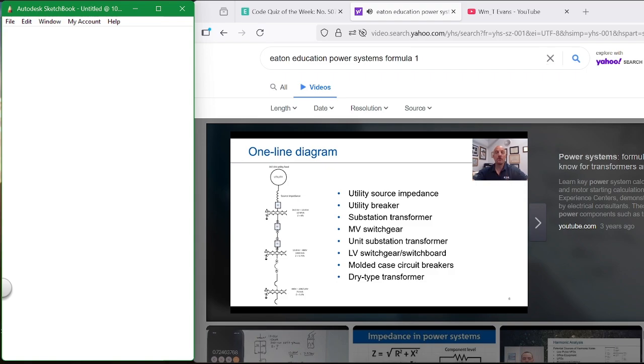So as a consultant, why do you need a one-line diagram like this one? Well, it's really important. If you're going to try to do calculations, you really need to have a good understanding of the actual numbers of values for the equipment. And there's two things associated with that that are important. One is you don't always immediately trust the one line. You have to make sure that it's accurate. But the second thing is really to make sure that you have all the data that's on the one line that matches up with your equipment. So sometimes you have to field verify, again, through nameplates on equipment and so forth.